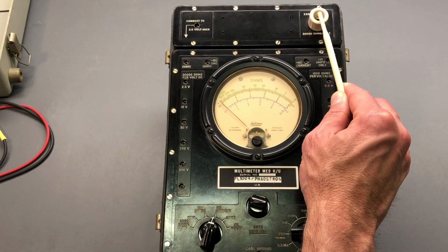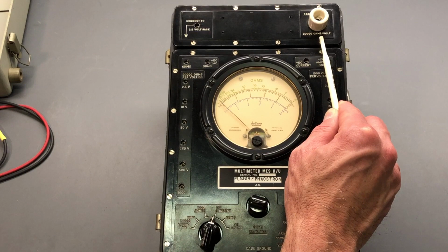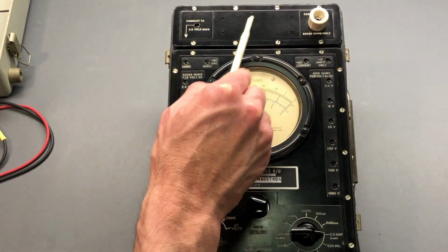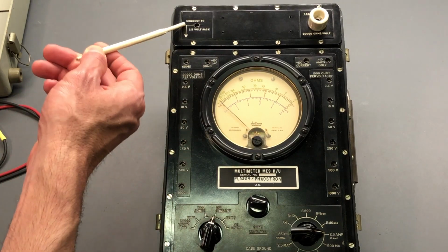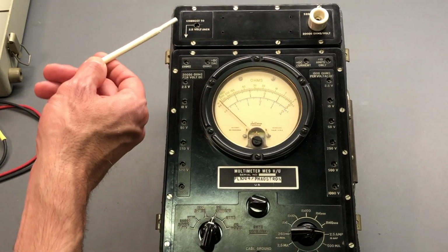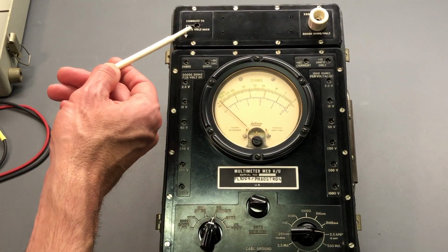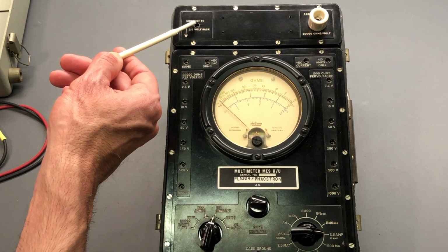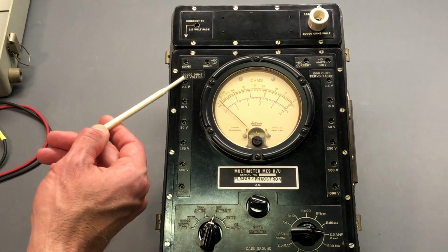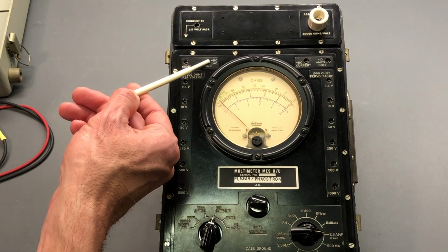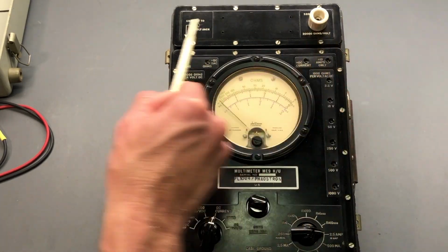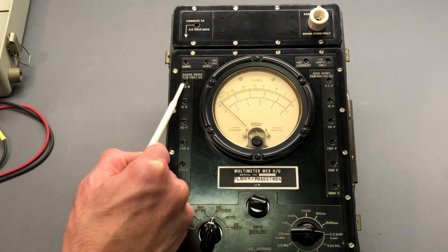So we have 5,000 volts over here. It is rated 20,000 ohms per volt, so very high impedance. This is basically a very high value resistor that's inside of here. And on this side, if you do want to use this function, it says connect to 2.5 volt jack. So you have a short jumper that goes from here to right here. Okay, so your negative probe again is on this jack. Your high voltage test probe is here, and this is jumped over to the 2.5.